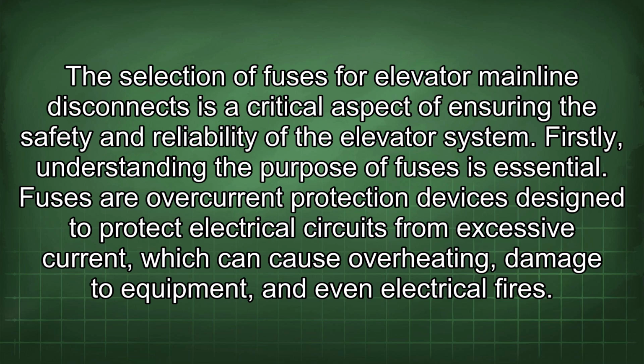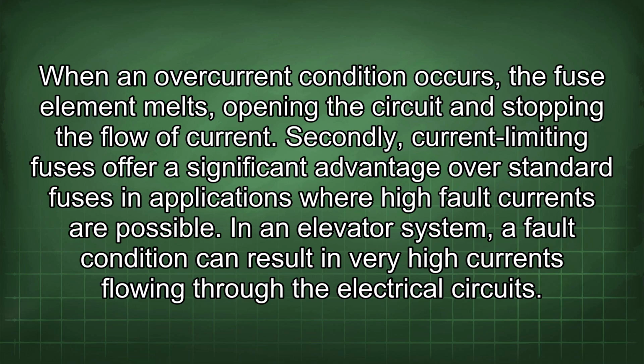The selection of fuses for elevator mainline disconnects is a critical aspect of ensuring the safety and reliability of the elevator system. Firstly, understanding the purpose of fuses is essential. Fuses are overcurrent protection devices designed to protect electrical circuits from excessive current, which can cause overheating, damage to equipment, and even electrical fires. When an overcurrent condition occurs, the fuse element melts, opening the circuit and stopping the flow of current. Secondly, current-limiting fuses offer a significant advantage over standard fuses in applications where high fault currents are possible.